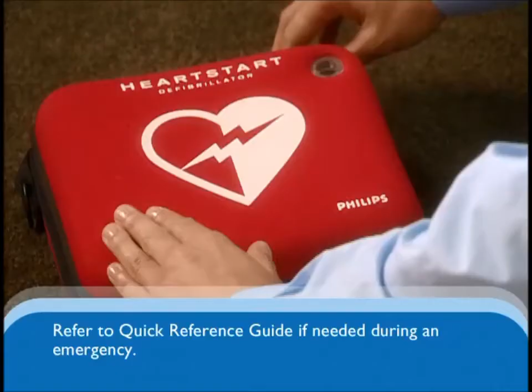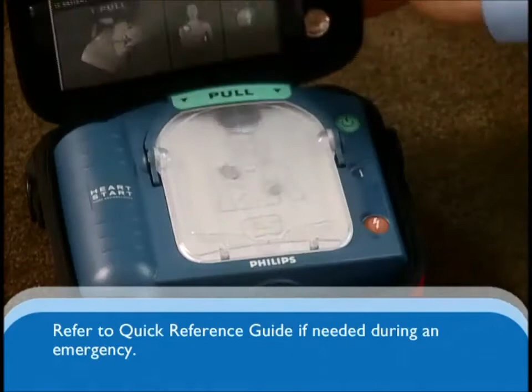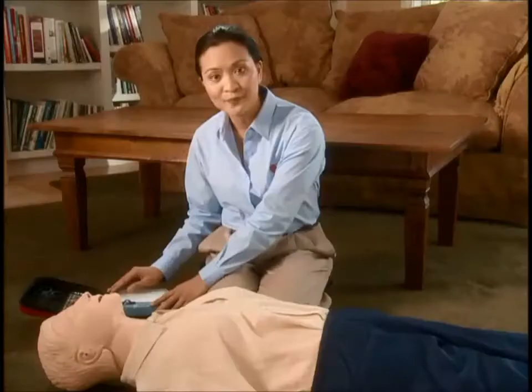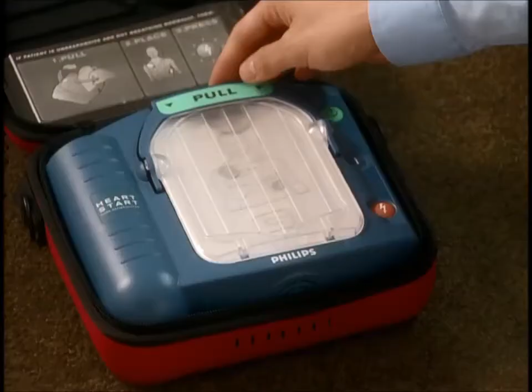Place the device on the same side of the person that you are on and open the case. First, you'll pull up on the green handle to remove the hard cover. Now this will turn on the defibrillator. You can also turn it on by pressing the green on-off button. Then the device will start giving you clear voice instructions, paced to allow you time to respond to each step. Begin by removing all clothing from the patient's chest. Cut clothing if needed. Quickly bare the person's chest by lifting, tearing, or cutting any clothing, using the scissors provided if necessary.